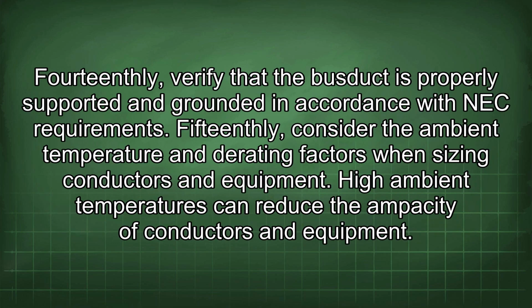14thly, verify that the busduct is properly supported and grounded in accordance with NEC requirements. 15thly, consider the ambient temperature and derating factors when sizing conductors and equipment. High ambient temperatures can reduce the ampacity of conductors and equipment.